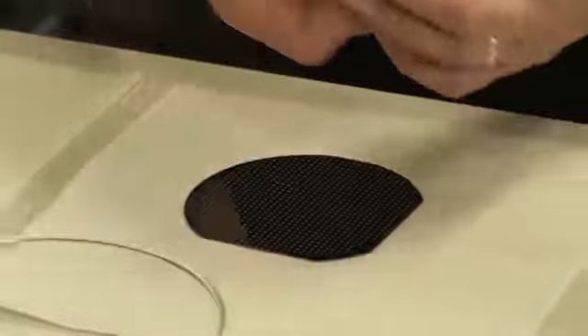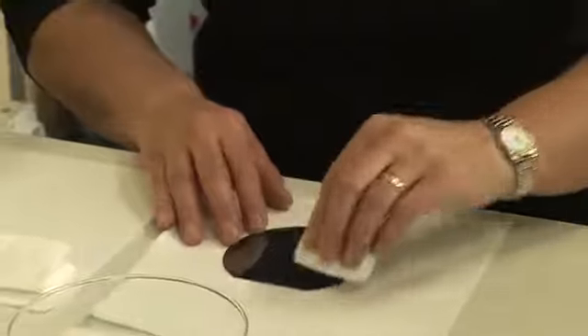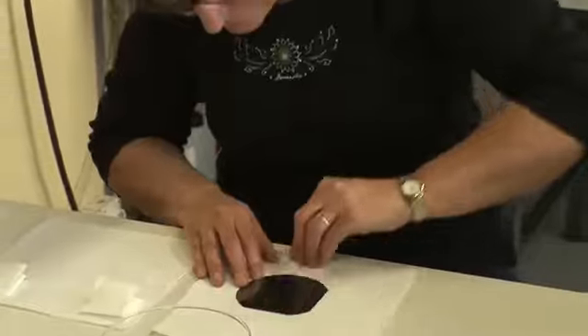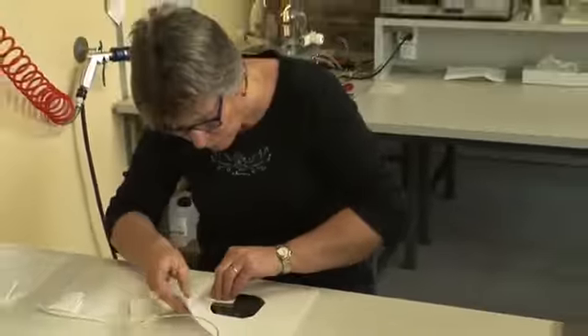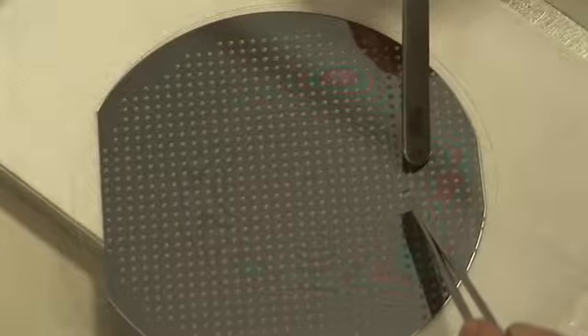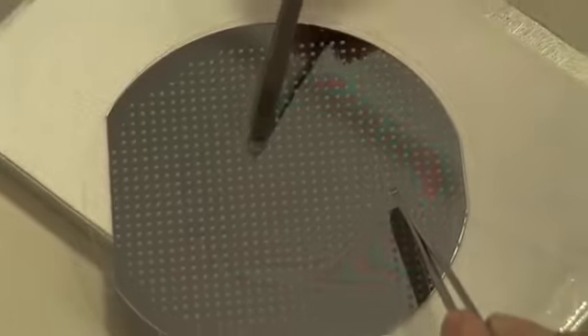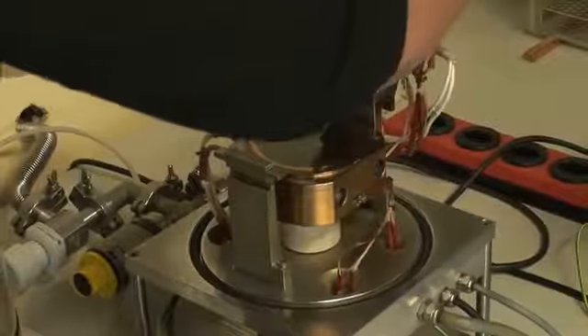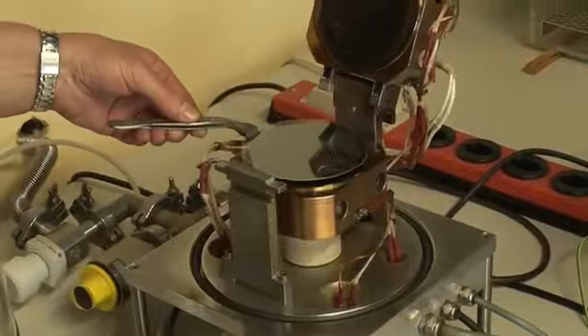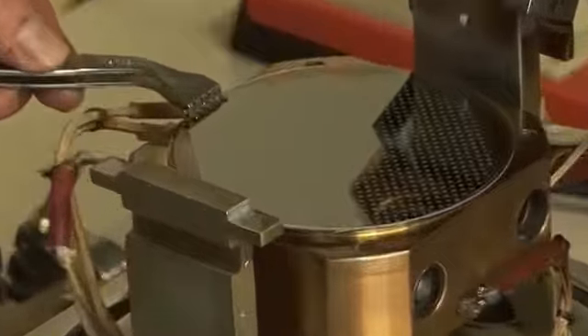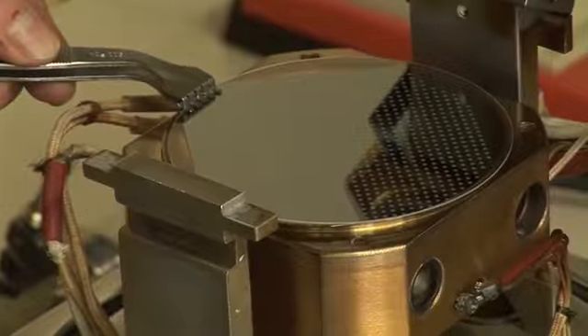The sensor's reference point is now fixed by attaching a glass disc to the back of the silicon. Before doing this, the two discs are cleaned carefully and thoroughly. This is vital to ensure successful bonding of the glass and silicon later on. Next, the two discs are bonded together under vacuum using electricity and heat. This technique is commonly known as Mallory bonding.